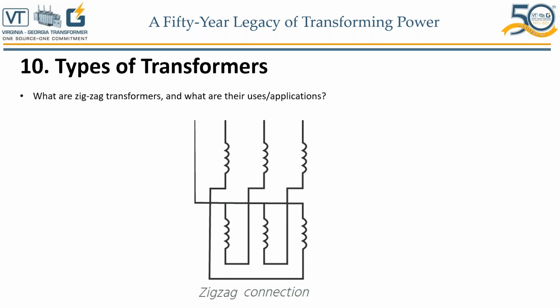A zigzag transformer is a special purpose transformer where the winding ends are connected as an interconnected star. Just think about a simple delta Y transformer. On the low voltage side, you have a start and a finish. You take the finishes and make the neutral, and you take the starts, depending on the vector group, to the bushings, and they become X1, X2, X3, and X0. In zigzag transformers, each output is a vector sum of the two phases offsetting each other by 120 degrees. So on each leg, you actually have, in a way, two different windings. I'll explain that in a minute.